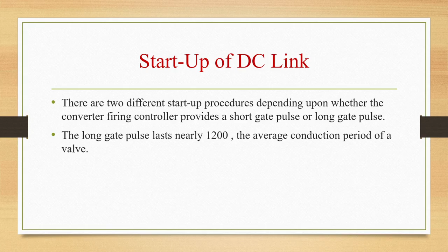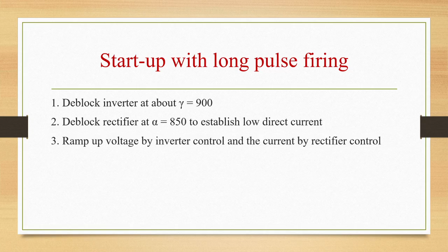Startup with the long pulse firing. So in this case, current extinction during the startup is not a problem. Starting sequence in this case is as follows. First, deblock the inverter at about gamma equal to 90 degrees. Second, deblock the rectifier at alpha equal to 85 degrees to establish low direct current. Third, ramp up voltage by inverter control and current by rectifier control.